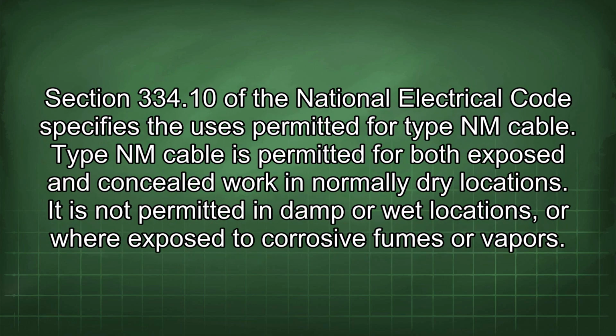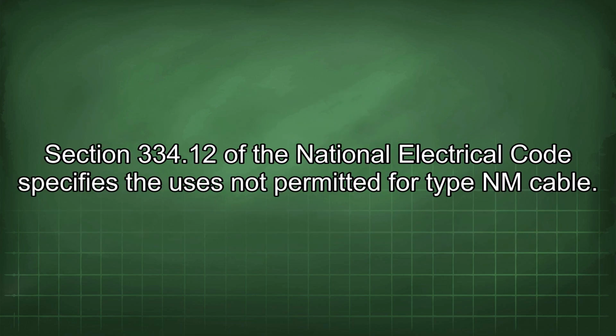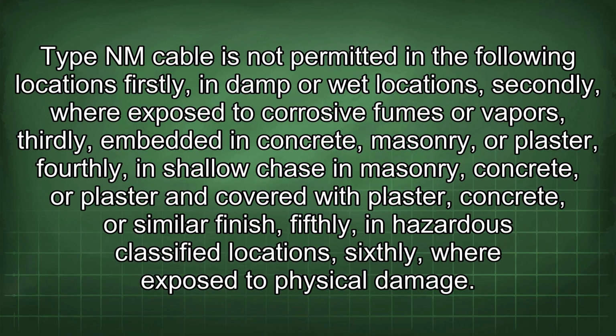Section 334.10 of the National Electrical Code specifies the uses permitted for Type NM cable. Type NM cable is permitted for both exposed and concealed work in normally dry locations. It is not permitted in damp or wet locations or where exposed to corrosive fumes or vapors. Section 334.12 of the National Electrical Code specifies the uses not permitted for Type NM cable. Type NM cable is not permitted in the following locations: firstly, in damp or wet locations; secondly, where exposed to corrosive fumes or vapors; thirdly, embedded in concrete, masonry or plaster; fourthly, in a shallow chase in masonry, concrete or plaster and covered with plaster, concrete or similar finish; fifthly, in hazardous classified locations; sixthly, where exposed to physical damage.